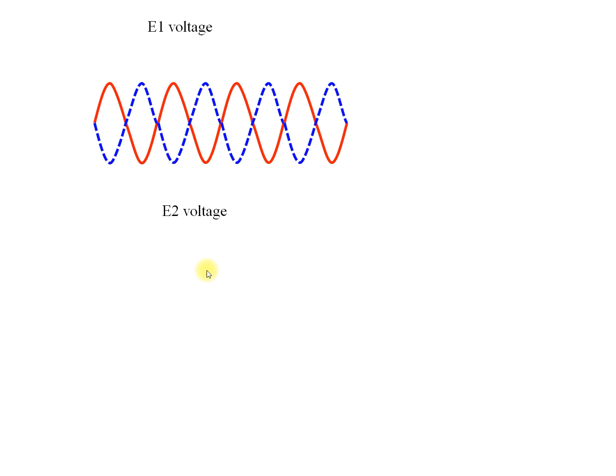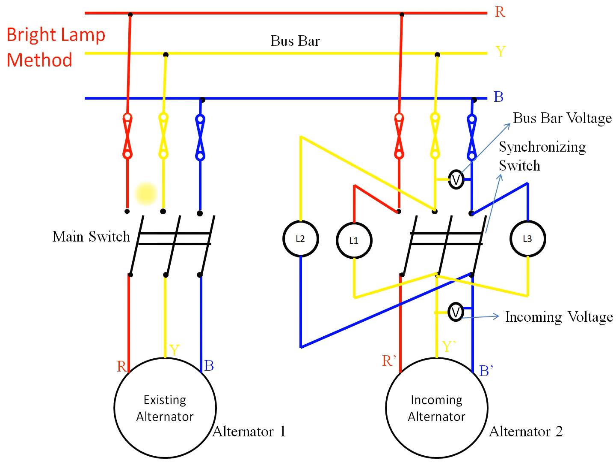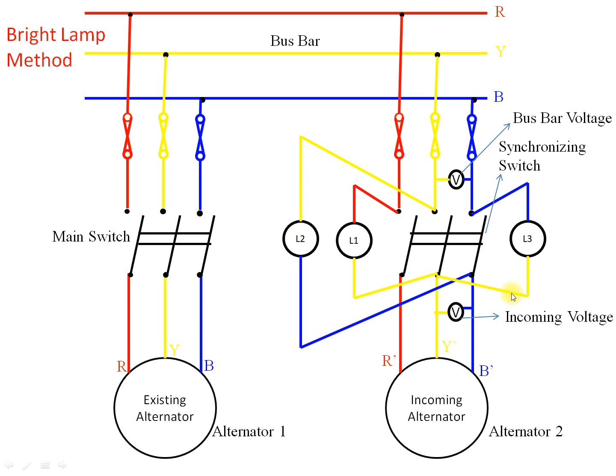Next, we are going to have the bright lamp method. In order to overcome the demerits of the dark lamp method, we come across this bright lamp method. Here we connect the incoming alternator to the existing one as shown in the figure. We connect lamp L1 across the red of the first and the yellow of the second, L2 across the yellow of the first and the blue of the second, and L3 from the blue of the first and the yellow of the second. The lamps are cross connected, and they will glow brightest when the two voltages are in phase. So we conclude that V1 is equal to V2.